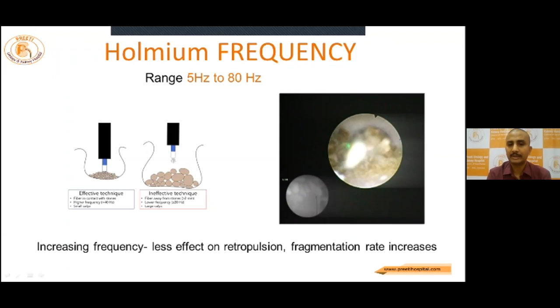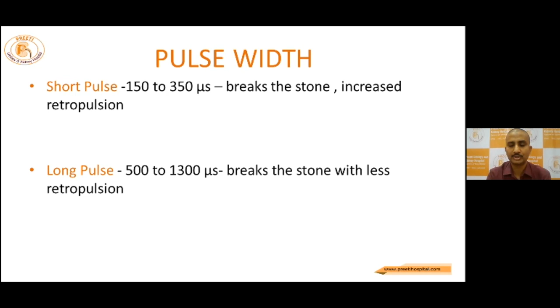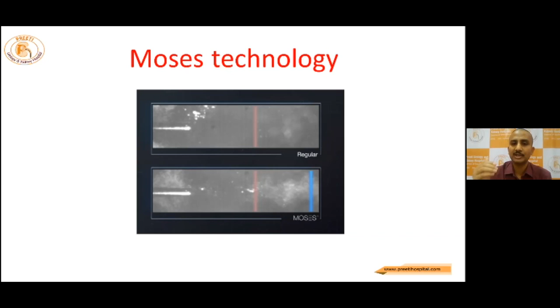So pulse width, that is short pulse and long pulse. Short pulse is 150 to 350 microseconds. It breaks the stone, but there is increased retropulsion. Whereas in long pulse, that is around 500 to 1300 microseconds, it also breaks the stone, but there is less retropulsion. So Lumenis came up with this Moses technology, where they have used the two bubble effect to drag the stone towards the laser fiber to fragment it in a much better way and reduce the retropulsion rates.